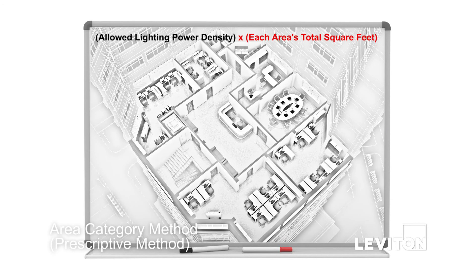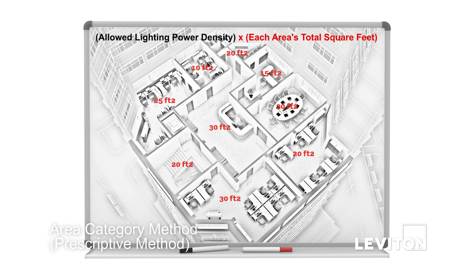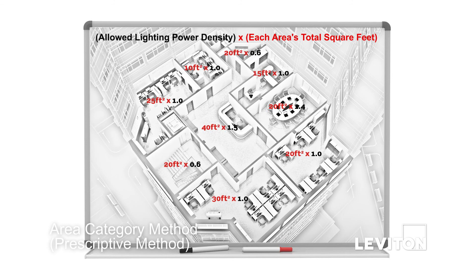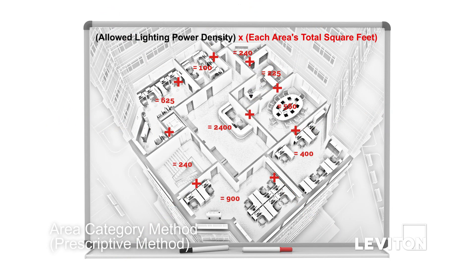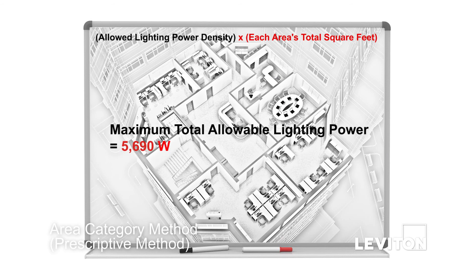To illustrate the process: first, identify all areas within a building. Second, identify the square footage for each area. Third, look up the allowed lighting power density value. Fourth, multiply the allowed lighting power density value in wattage for each area by the total number of square feet in each area. And fifth, add the total for each area together to determine the total allowable lighting power.